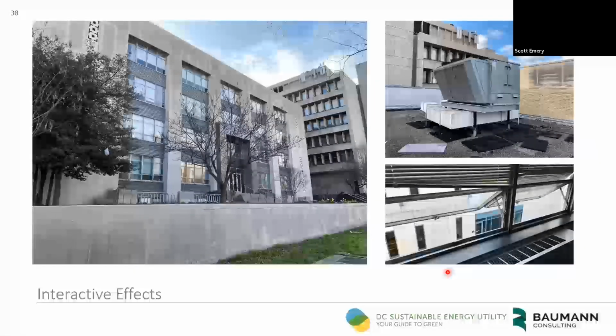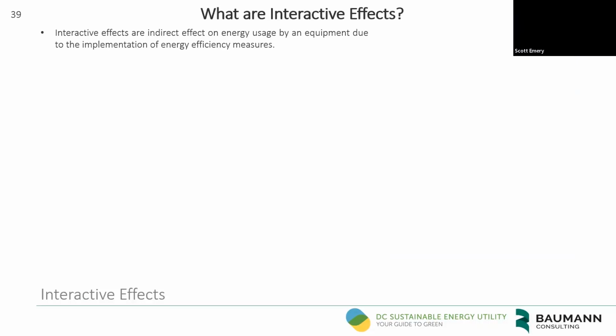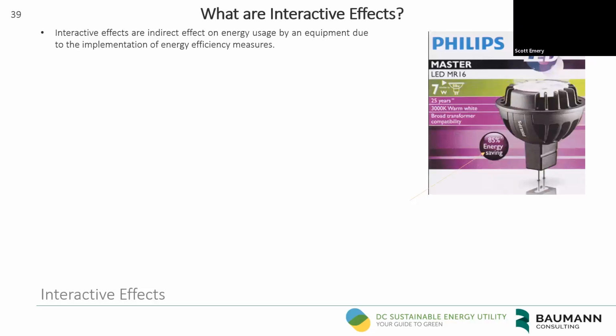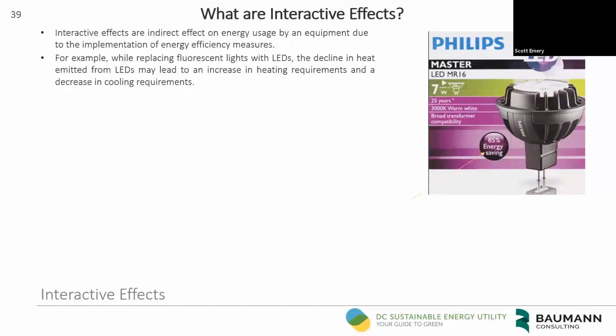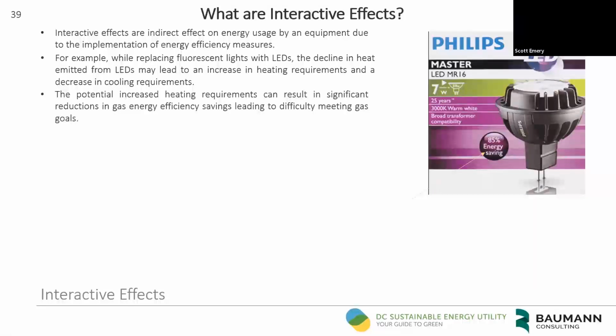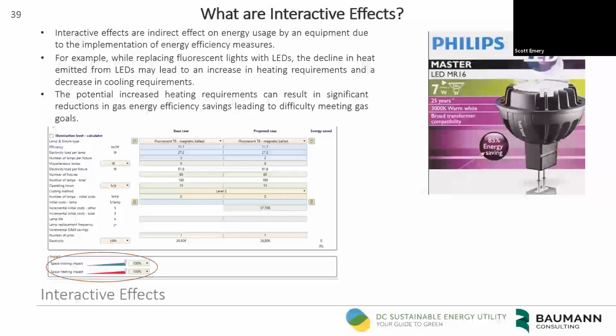Whenever we do the tables in the normal forms, you see that everything is calculated in a vacuum. In this particular scenario, we're going to talk about interactive effects. A good example would be lighting. If it's a fluorescent light or something like that, there are heat effects with it. When you convert them over to LED, there's less heat, right? So the potential increased heating requirements can result in a significant reduction in gas energy savings, leading to difficulty meeting gas goals. So here's a diagram showing that.